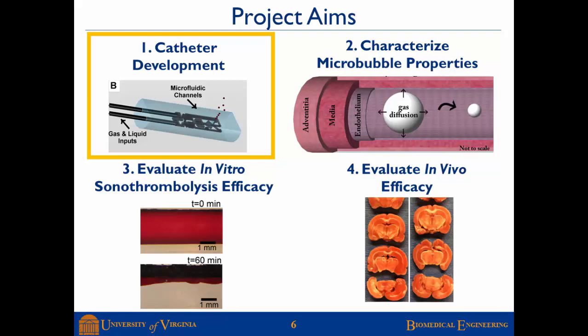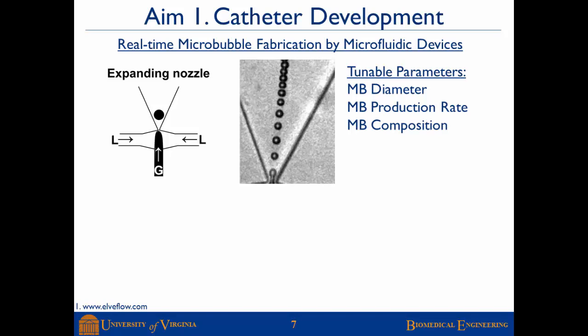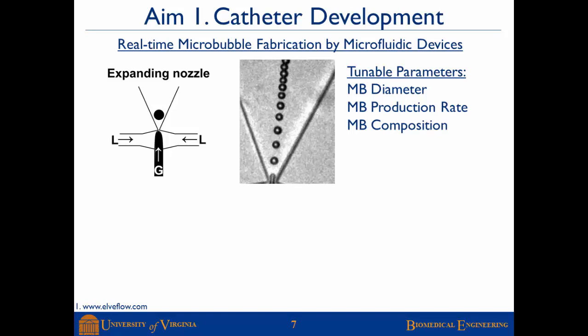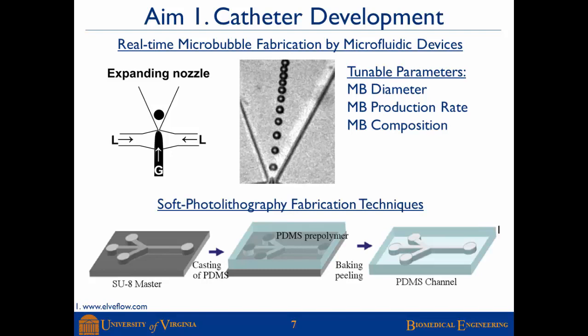For aim one, the catheter we designed has a microfluidic device placed on its tip — a flow-focusing microfluidic device in which two liquid channels pinch a gas channel to produce microbubbles. This is attractive because by changing the liquid or gas pressure, we can change the microbubble diameter, the production rate, and the composition by changing the gas or liquid phase.